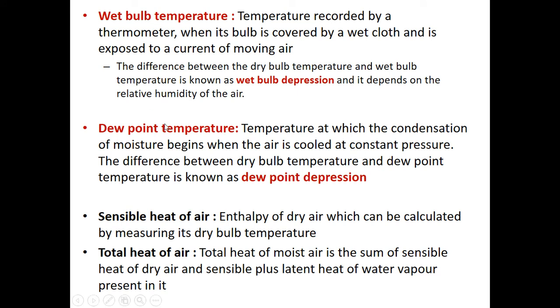Dew point temperature is the temperature at which condensation of moisture begins when the air is cooled at constant pressure — that is, vapor converting to liquid. The difference between DBT and WBT is called wet bulb depression. Similarly, the difference between the dry bulb temperature and the dew point temperature is called dew point depression.